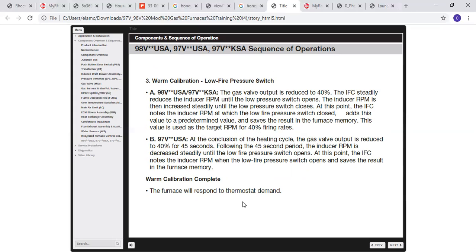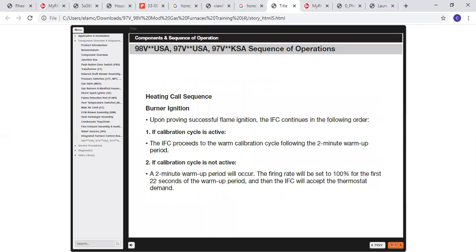If you have a call for heat during this cycle, it will not be interrupted. You cannot stop or override the calibration sequence. Generally speaking, whenever you first power up the furnace, it's going to go through this calibration sequence, and you just have to let it do its thing. Not much you can do to stop it. But if you have a call for heat, as soon as it finishes warm calibration, it'll go right into your heat call for you.